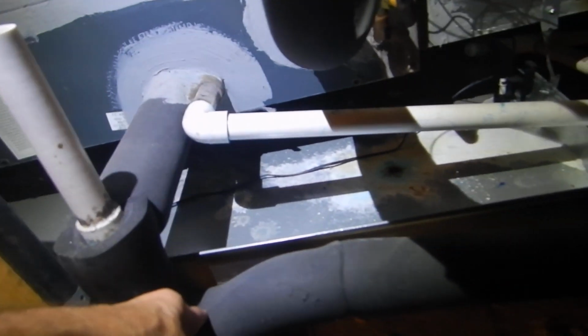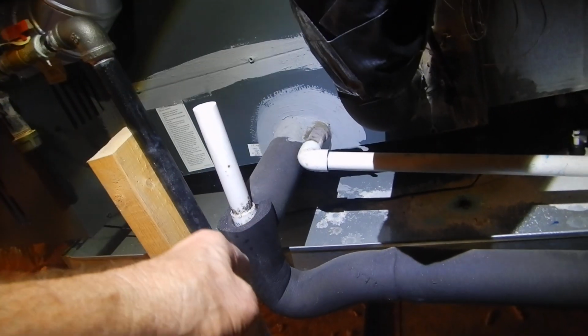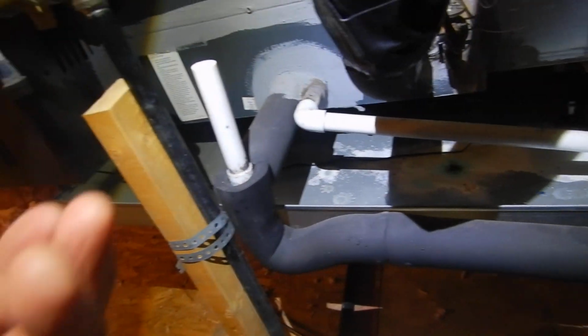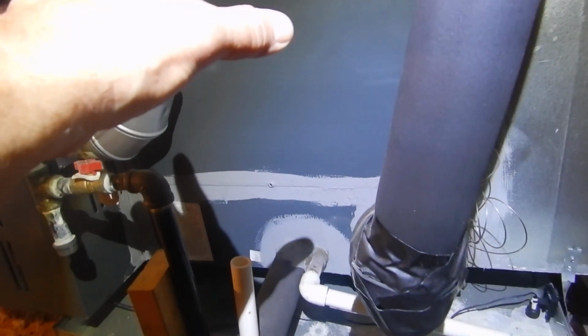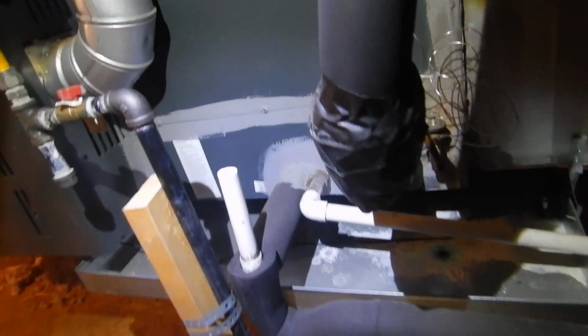But this is a shallow trap, so it's self-clearing. Not self-cleaning, but self-clearing. It'll still clog. So what happens is the water comes down here like a roller coaster. The last car follows the first, swoosh, like a yogurt commercial, and it opens this up. Where does this go? This goes to the sewer. So then the sewer gases can migrate their way back up here, and that'll be an open vent right there. Some of them will come into the attic, but they're going to come up here and accumulate inside your evaporator coil plenum. And then when the air conditioner kicks on, they're going to be distributed evenly throughout the house. You won't smell it because it'll be so diluted. But all the cooties and all the pathogens will be distributed through your house.